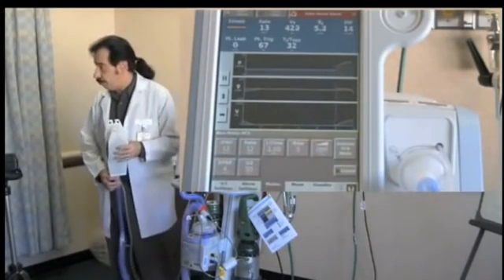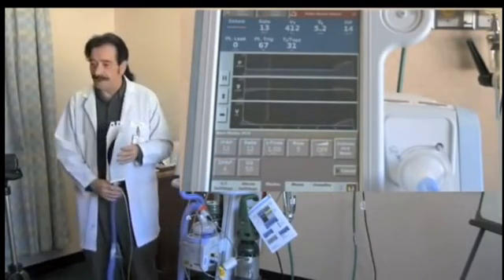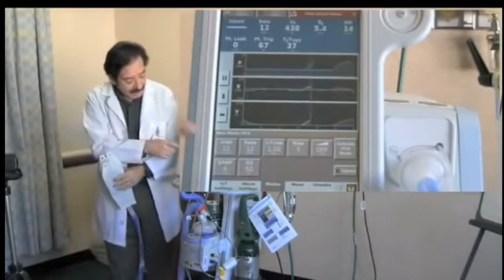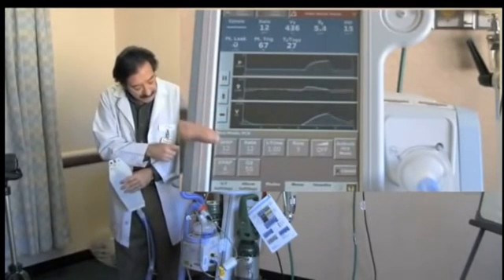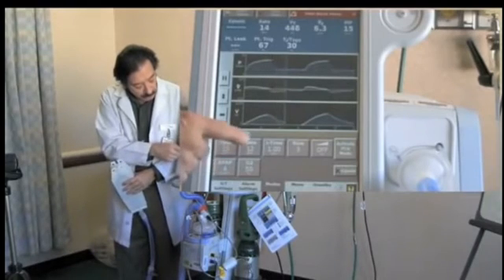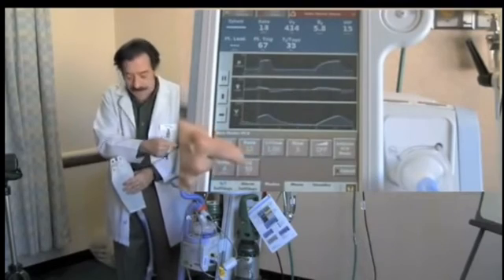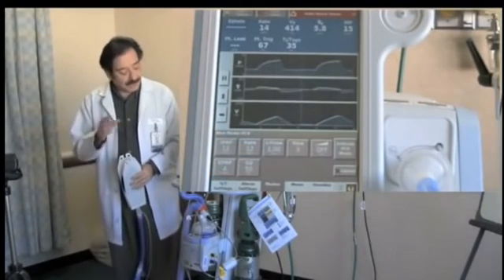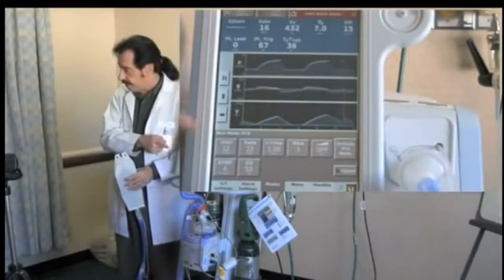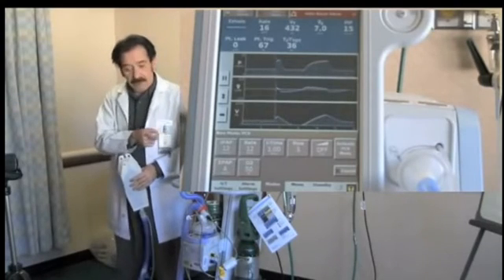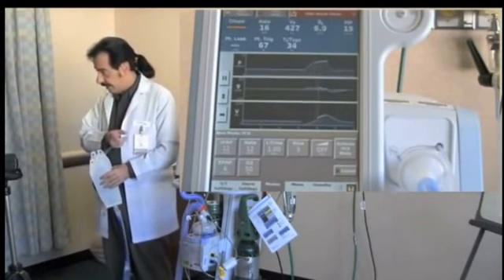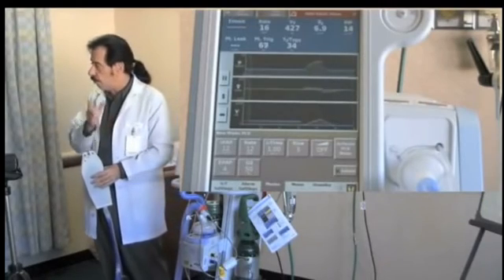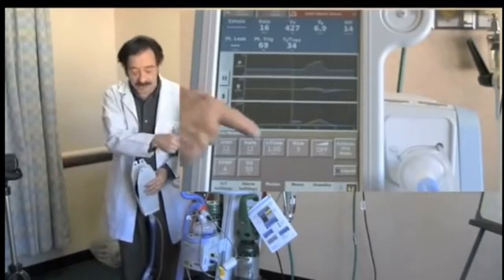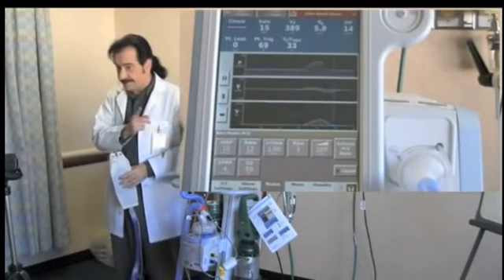Next mode we have available is called pressure control ventilation. That's what it is, pressure control ventilation with a non-invasive ventilator. Here again, it looks like the ST mode. I set the IPAP and the EPAP, the rate, the I time, the rise, ramp if I want to use it, and FiO2. Now, in this case, it's really important to set the I time appropriate for the patient, because every breath that the machine gives, whether it's patient triggered or time triggered, will conform to this I time. Every breath will be the same.